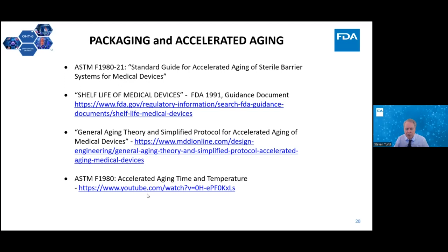And choosing some information from those references. This is from our guidance document and also from another company's general guidance online. As a rule of thumb, for every 10-degree increase of the tested temperature above normal storage temperature will decrease the time needed, increasing the expiration date by a factor of 2. Okay, we're talking about accelerated aging. The Arrhenius equation is what's behind this. Sometimes you may hear it referred to as Van 't Hoff's, and he's the guy who trained Arrhenius, basically, or Arrhenius learned from him. The Arrhenius equation indicates that for every 10 degree C increase in temperature, you get a doubling of the chemical reaction rates. And this is known as a Q10 of a factor of 2. Some materials have higher or lower reaction rates, Q10 factors. So that's important to know.